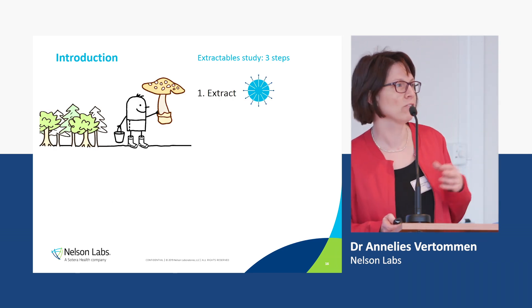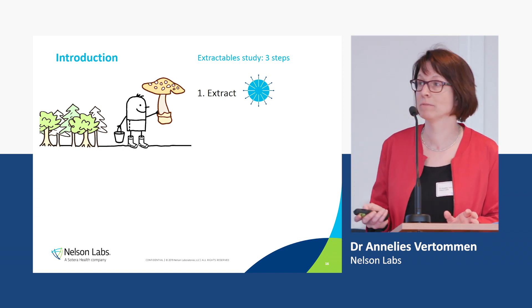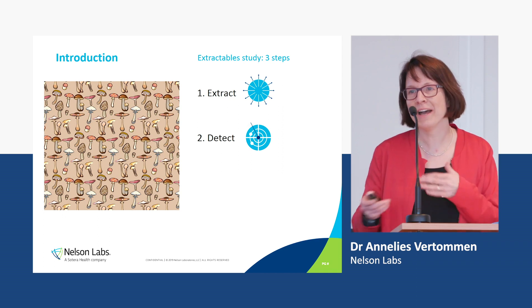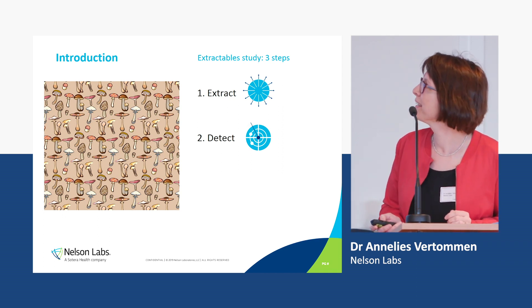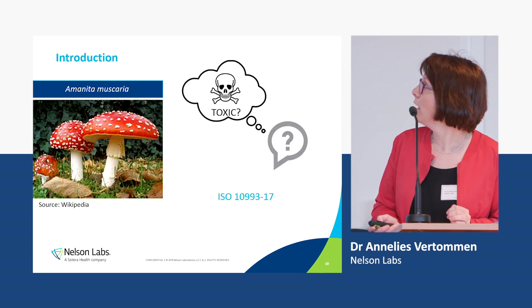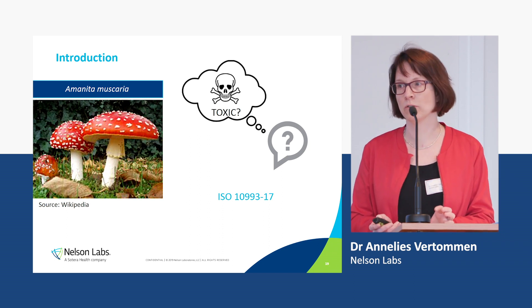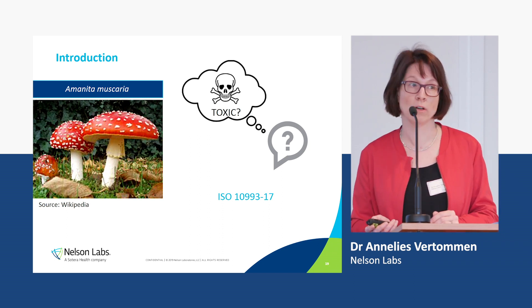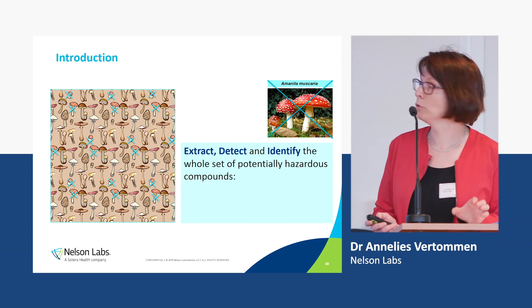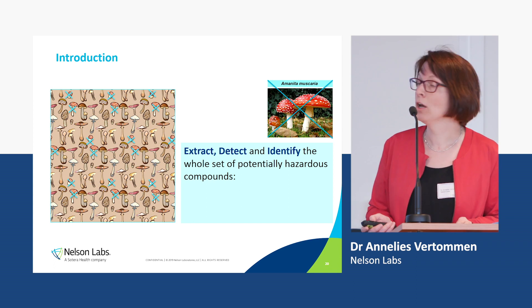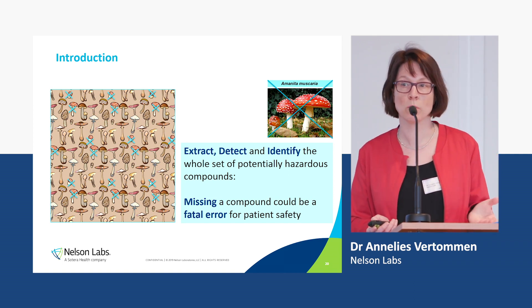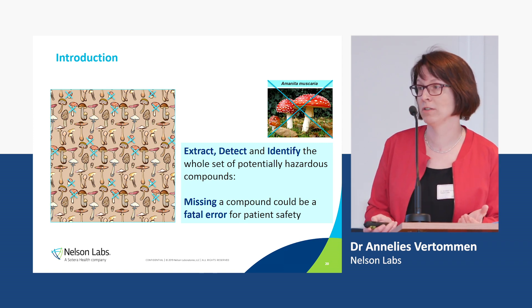The first step is you need to extract your compounds from your medical device. The second step is to detect them. And the last step is you need to identify the compounds. A toxicologist will then check whether or not these compounds are toxic. It's important to complete all three steps: extract, detect, and identify the whole set of potentially hazardous compounds — because missing a compound means the toxicologist will not assess it, which could be a fatal error for patient safety in the worst case.